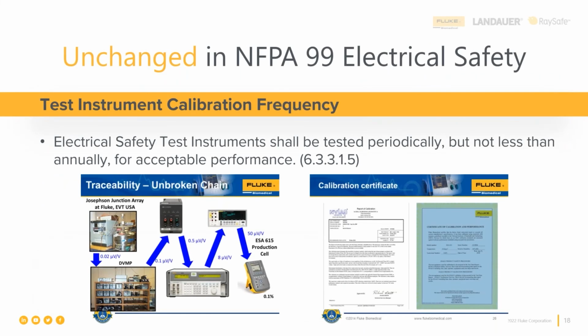All right, unchanged in NFPA 99: calibration frequency of your test instrument. The electrical safety test instrument shall be tested periodically, but not less than once per year, for acceptable performance. That's your test equipment. So if you're doing NFPA 99 and you're not sending your test instrument out for calibration once per year, you're not really following this guideline. And on audit trail, it is discoverable. So we certainly provide that for our electrical safety analyzers and other test instruments that you may be using. And you can request, and you're well advised to request, as-found data, so you know whether it stayed in tolerance or not during the last calibration cycle.